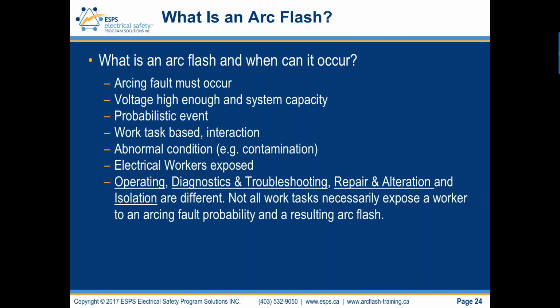The last bullet says, with respect to arc flash, we need to consider operating, diagnostics and troubleshooting, repair and alteration, and isolation. These are four different things. And I'll provide another slide coming up to give more information. But that's what we need to define: these four different individual groupings of work tasks. And not all work tasks necessarily expose a worker to an arcing fault probability and a resulting arc flash. We need to get back to that because industry has evolved to believe that normally operating energized electrical equipment has a high probability of an arcing fault and an arc flash, and that is not true.